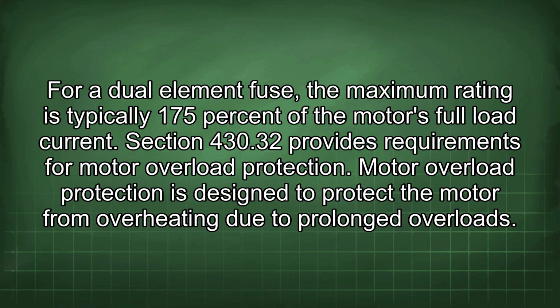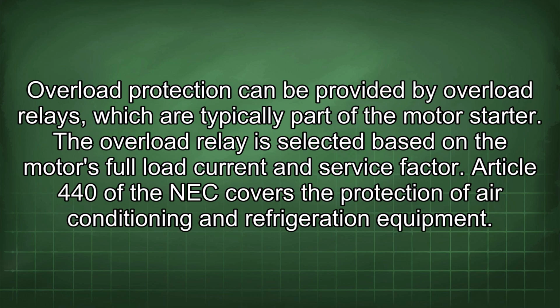Section 430.32 provides requirements for motor overload protection. Motor overload protection is designed to protect the motor from overheating due to prolonged overloads. Overload protection can be provided by overload relays, which are typically part of the motor starter. The overload relay is selected based on the motor's full load current and service factor.